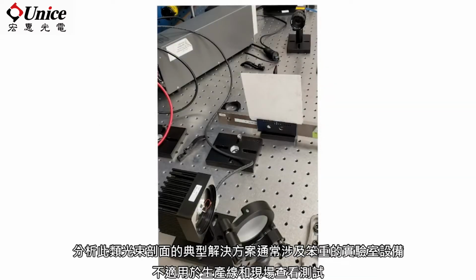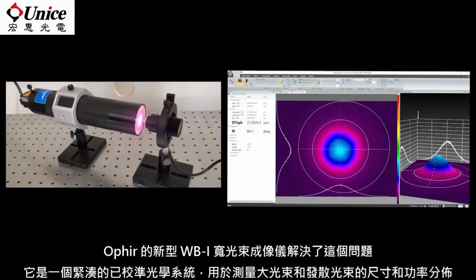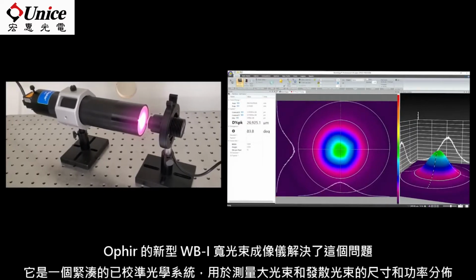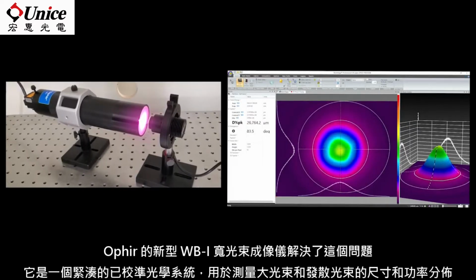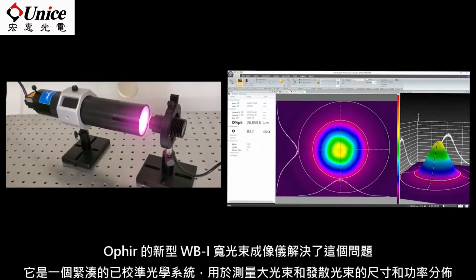Typical solutions for analyzing such beam profiles usually involve bulky laboratory equipment which is not suitable for use in production lines and in situ tests. The new WBI wide beam imager from Ophir solves the problem. It's a compact calibrated optical system for measuring the size and power distribution of large and divergent beams.